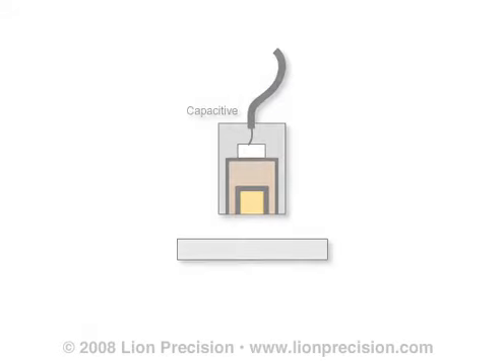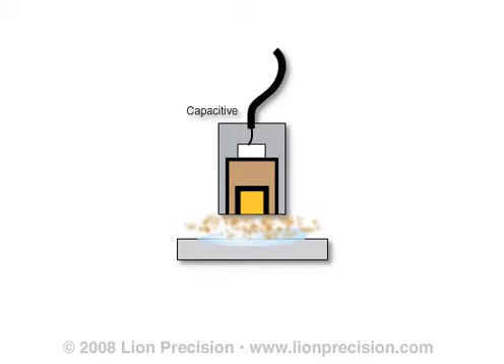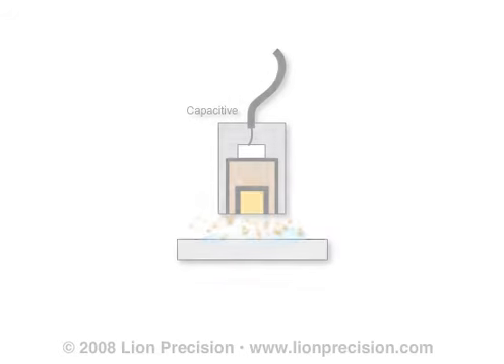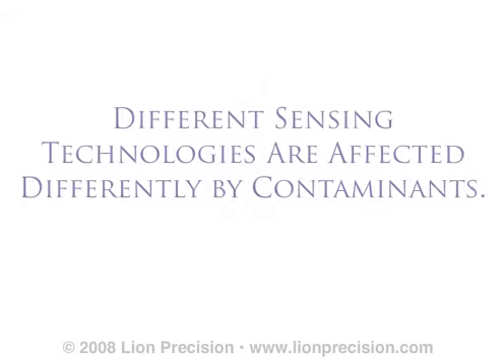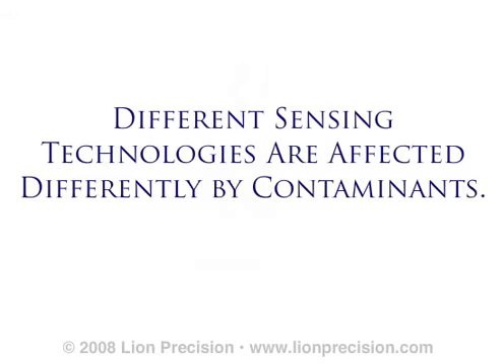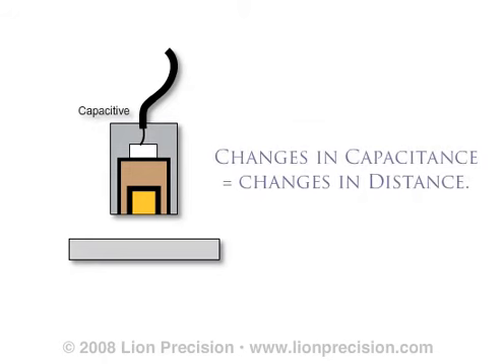In some applications, the gap between the sensor and target can become contaminated by dust, liquids such as coolant, or other materials which are not part of the intended measurement. How the sensor reacts to the presence of these contaminants is a critical factor in choosing between capacitive and eddy current sensors. Capacitive sensors assume that changes in capacitance between the sensor and the target are a result of a change in distance between them.